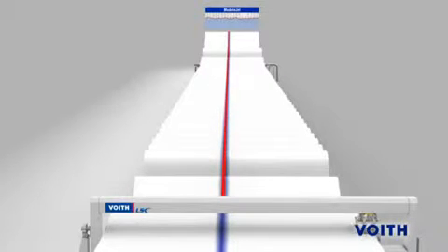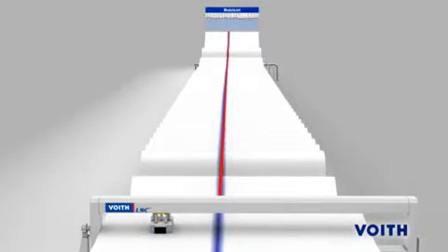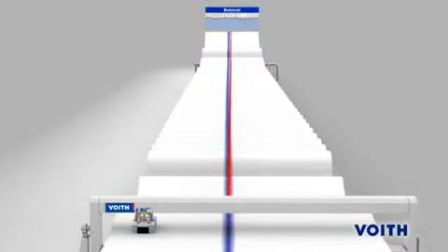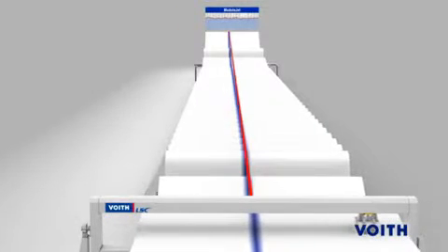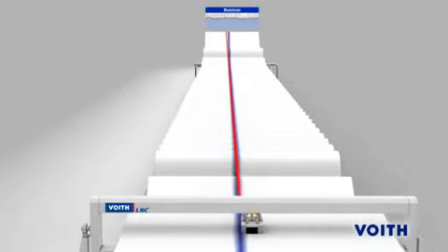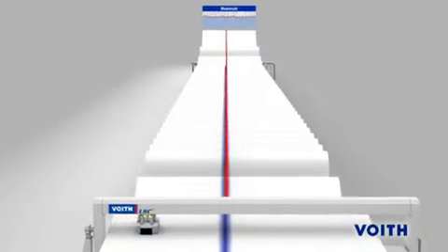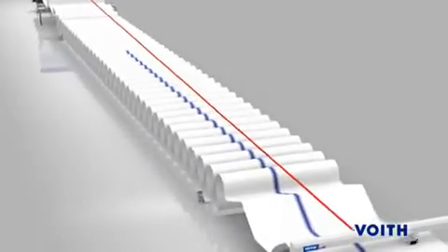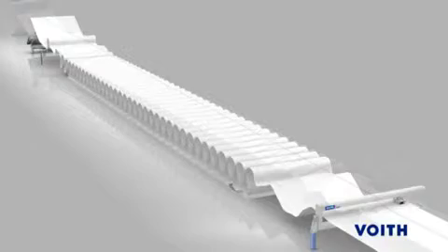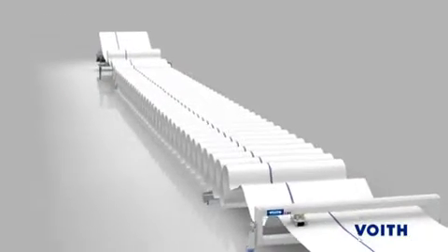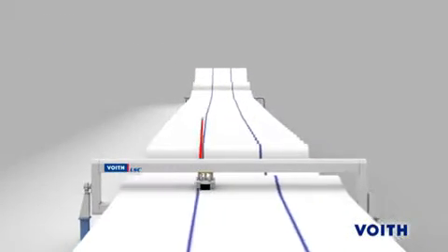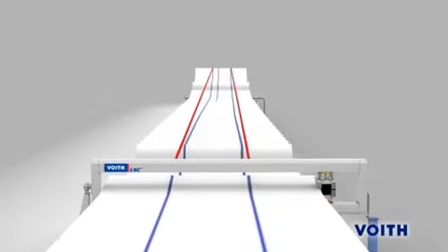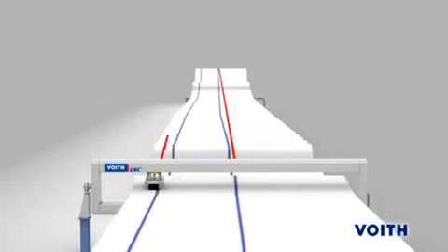With its intelligent automapping, the OnQ Profimatic control software recognizes web wandering, calculates the web offset and adapts the controller behavior appropriately to correct the CD profile. This correction is not carried out at a single position, but is adjusted in parallel with each control zone, considering the adjacent actuators.